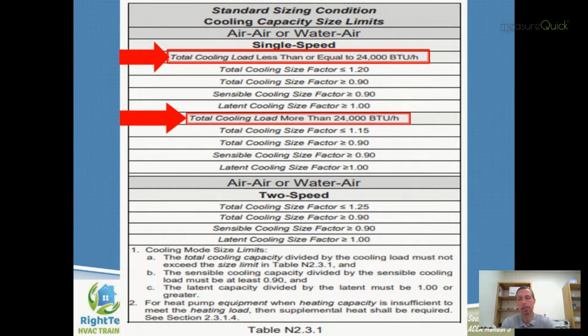So again, we go back to that smallest defensible load. We want to make sure that you can select something that, worst comes to worst, you can actually defend yourself on out there in industry. So I think that's a very important factor. I'll draw your attention down to the bottom of this chart where it talks about two-speed equipment, or two-stage might be a better word for that. But you'll notice your total cooling size factor now is up to a factor of 1.25.